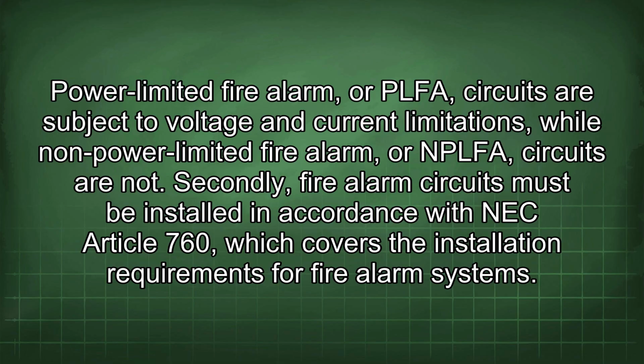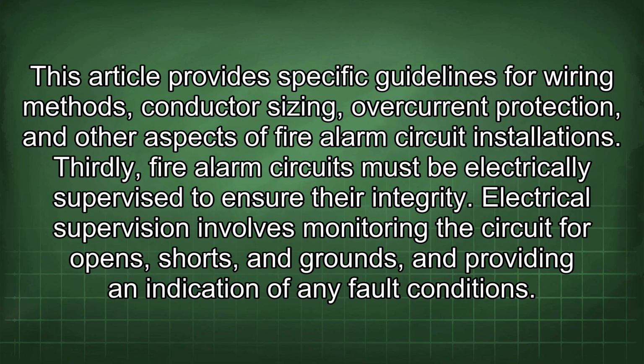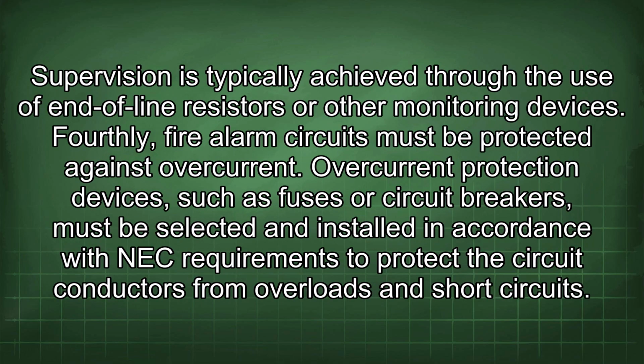Secondly, fire alarm circuits must be installed in accordance with NEC Article 760, which covers the installation requirements for fire alarm systems. This article provides specific guidelines for wiring methods, conductor sizing, overcurrent protection, and other aspects of fire alarm circuit installations. Thirdly, fire alarm circuits must be electrically supervised to ensure their integrity. Electrical supervision involves monitoring the circuit for opens, shorts, and grounds, and providing an indication of any fault conditions. Supervision is typically achieved through the use of end-of-line resistors or other monitoring devices.